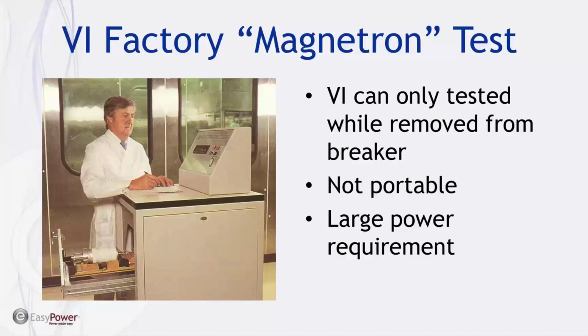The test that's performed at the factory requires that the vacuum interrupter be removed from the circuit breaker because they're testing them directly off the line. They have them loose and easy to test. So they simply open the contacts of the vacuum interrupter, place it inside of this device, and do this magnetron test that we talked about. One of the problems with applying this to testing vacuum interrupters in the field is that this device is not portable. It has a very large power requirement because they're applying a constant magnetic field, which requires a pretty large transformer. And also the vacuum interrupter has to be removed from the circuit breaker, which in most cases is not an option during maintenance and testing. Also, you risk doing damage to the vacuum interrupter by removing and replacing it.